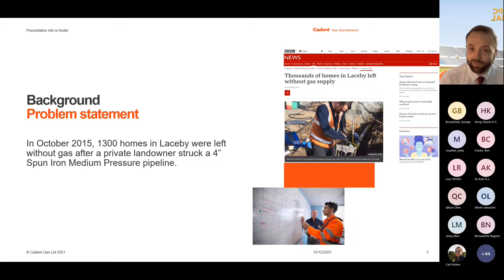In October 2015, around 1,300 homes were left without gas after a private landowner struck a 4-inch spun iron medium pressure gas pipeline laid in the 1950s across agricultural land. The 4-inch pipe was a single spur to the pressure reduction installation in the village, where gas is regulated down to low pressure. Where it was damaged, the pipe was operating at a depth of between 400 and 800 mil.